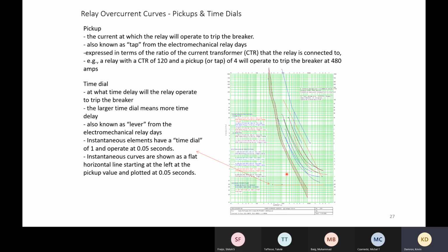So that's a good question. There's a number of different uses for them. Like I said, one of ours is a fuse saving scheme. Even if a fault is on a lateral past a fuse, every time that fuse blows, I've lost customers. So now I've got to have a crew go find the location. Hopefully they've got that fuse size on their truck, and then replace the fuse. If they don't have the fuse size on the truck, they have to go back to the main office, get that fuse, drive back out to the site, and put a fuse in. Well, for CAIDI, SAIFI, all of the reliability indices that our utilities are measured for, the longer someone's out, the worse off, right? Those numbers get worse.